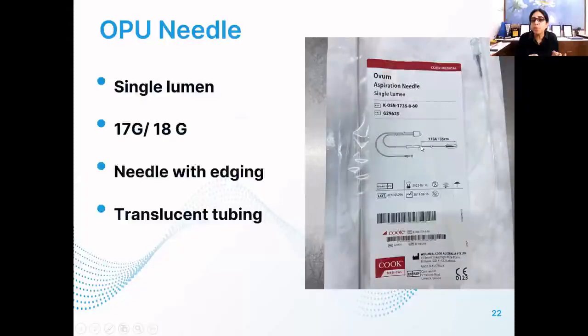All the needles are standardized. It's more or less the same. So this is the length of the needle, which is 35 centimeters. So when you have a 1735, 17 is the gauge, 35 is the length. The other option is a 30 centimeter needle, which is also available. So you have to see which you're more comfortable with. It is just that the longer the needle, the longer will be the travel path of the follicular fluid and the oocytes, and you're wasting 5 centimeters more of travel, leading to a drop of temperature. So maybe longer needles you need for obese patients, and otherwise you can cut down and use the 30 centimeter needle. So that's for you to decide.